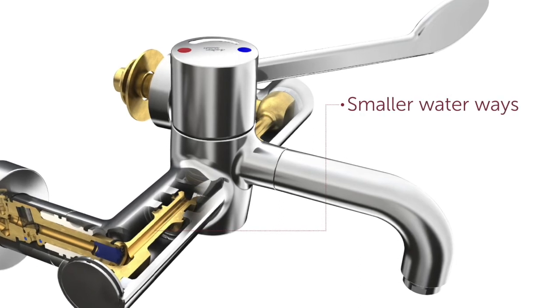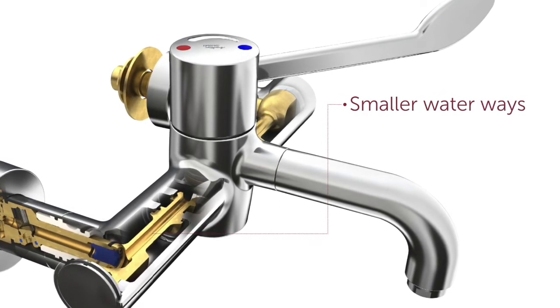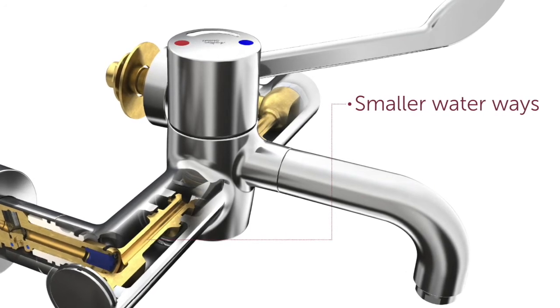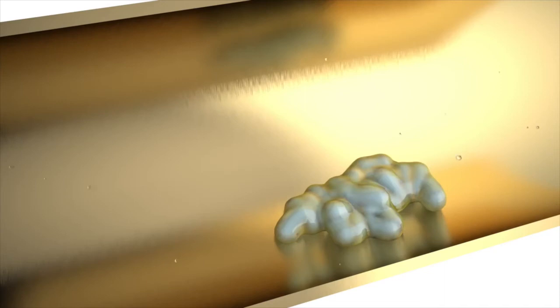Smaller waterways reduce the amount of water left in the tap and create greater velocity, which reduce bacterial attachment. We've also introduced smoother bore waterways, making it harder for bacteria to stick.